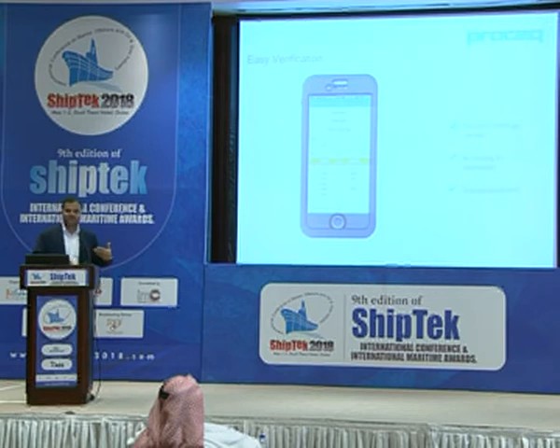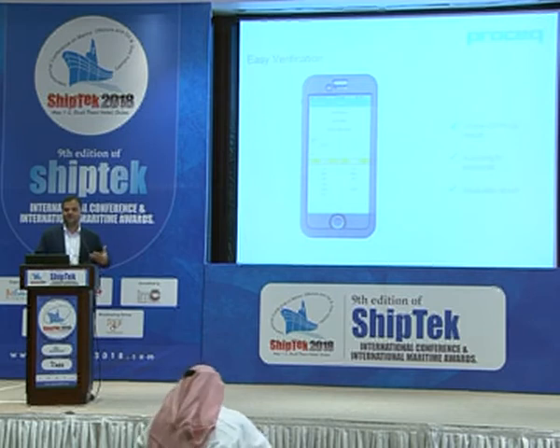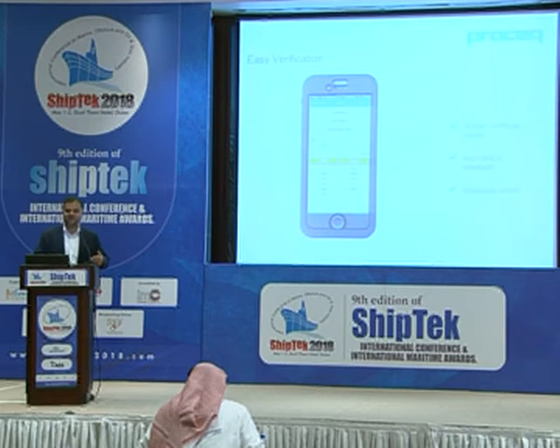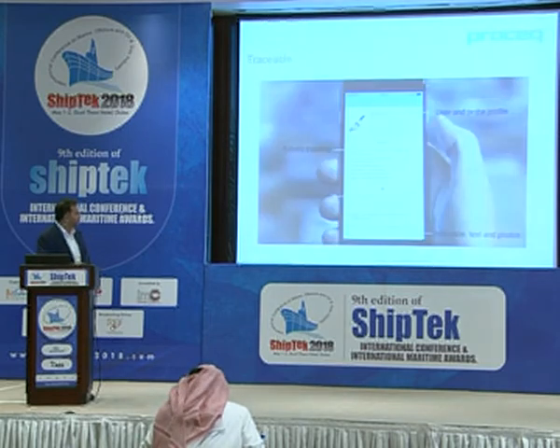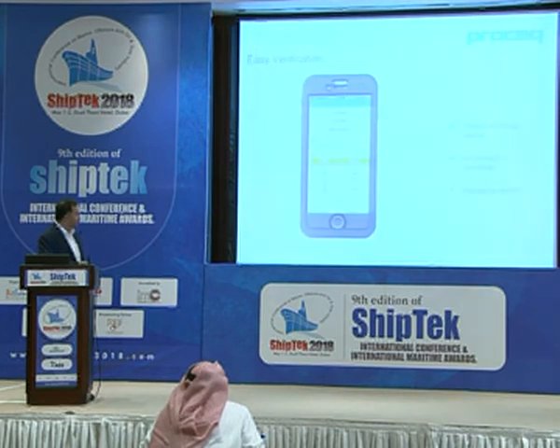Verification, as we spoke, verification is also very important, and the verification can also be done on our iOS device right on site, and we can save the verification data along with the test data. So here we can see the verification is done over here. It gives a green check mark, otherwise it gives a red cross which shows that verification failed.